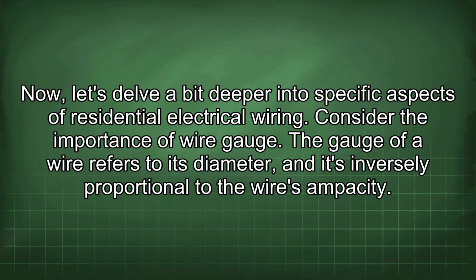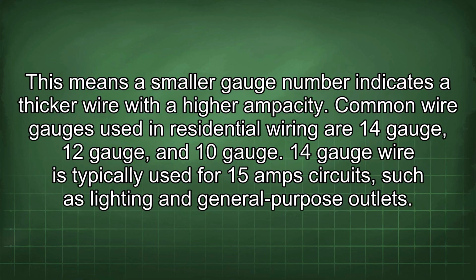Consider the importance of wire gauge. The gauge of a wire refers to its diameter, and it's inversely proportional to the wire's ampacity. This means a smaller gauge number indicates a thicker wire with a higher ampacity. Common wire gauges used in residential wiring are 14 gauge, 12 gauge, and 10 gauge.